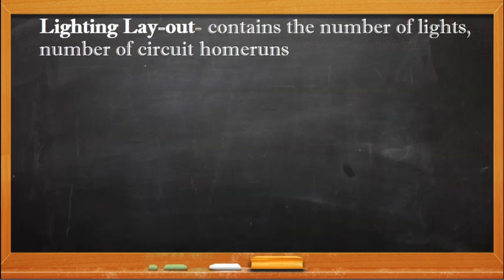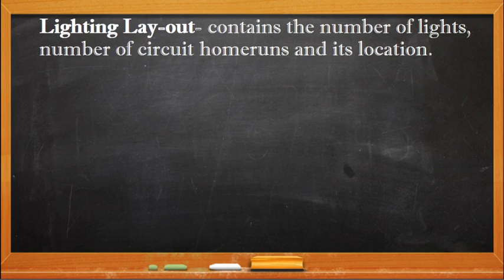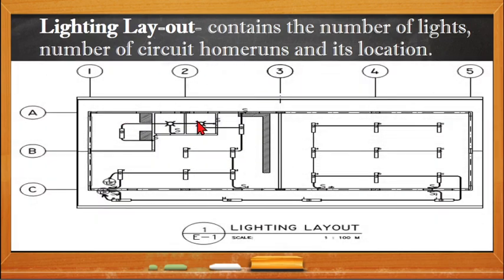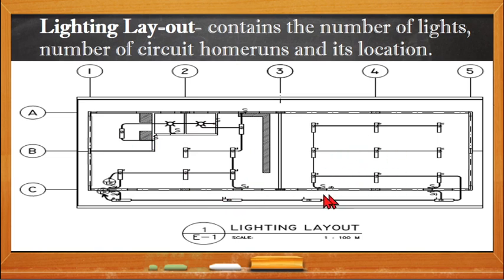The lighting layout contains the number of lights, number of circuit home runs, and their location. Here is an example of a lighting layout. These are the symbols for the lights. The lighting layout will also contain the switch and the location of the switch — the switch will be put on this side of the wall. We have two home runs, so we have two circuits and two circuit breakers.